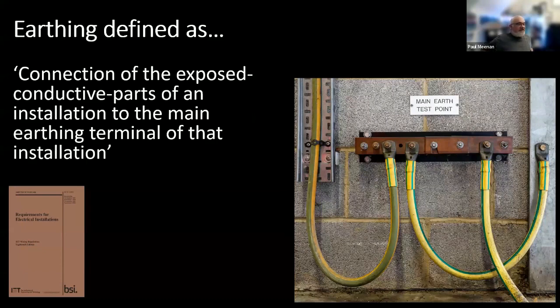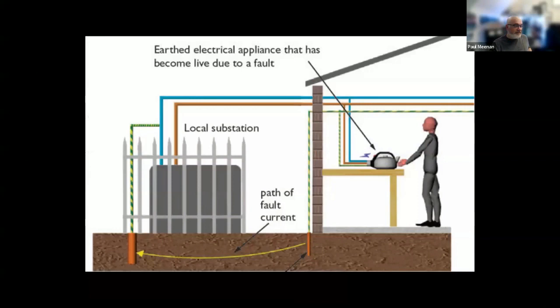Earthing is the connection of exposed conductive parts of an installation to the main earthing terminal of that installation. Okay, and that's a picture of an earth bar that I installed on a job where we bonded the steelwork and we had an earthing conductor and CPC. It was a heavy industrial job, as you could tell. I probably should have put that box in an enclosure to protect it from external influences. So we don't always get it right.